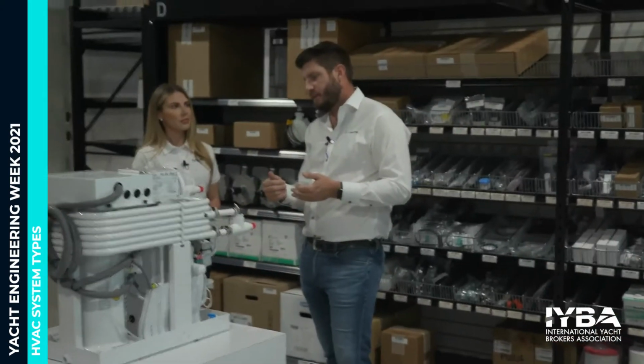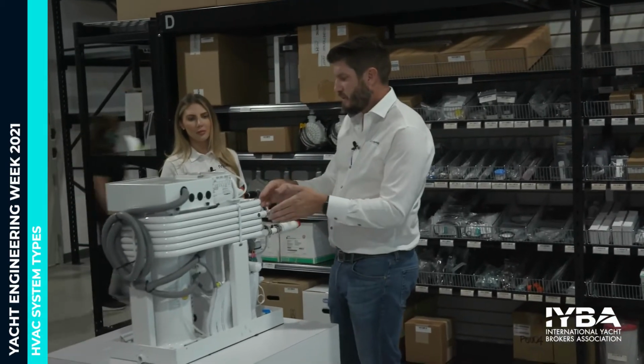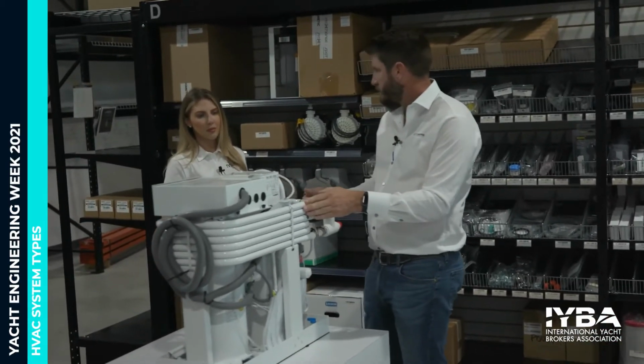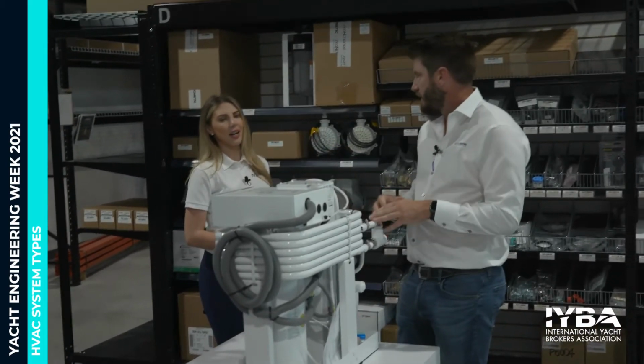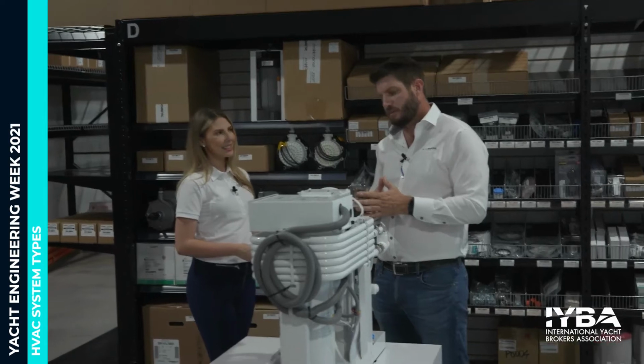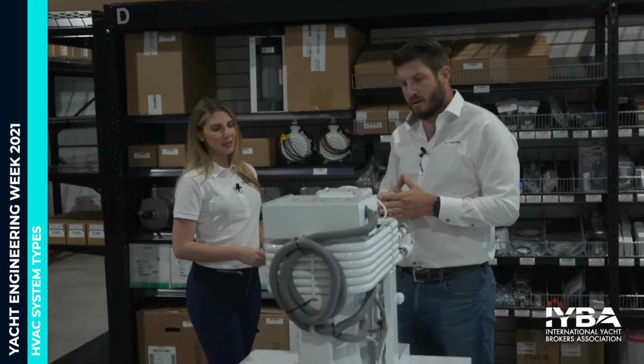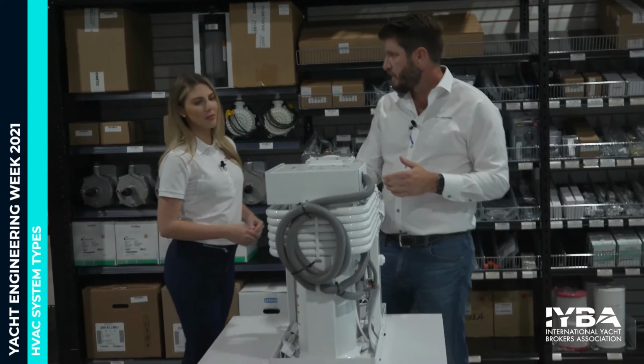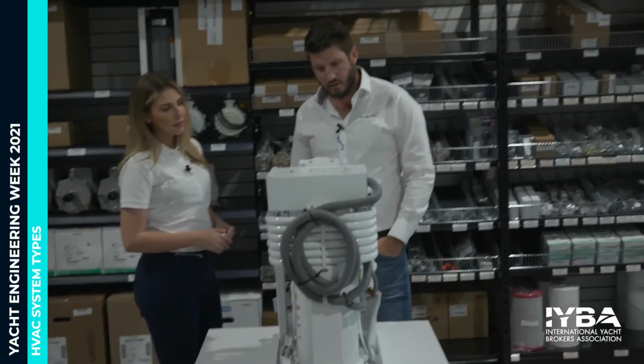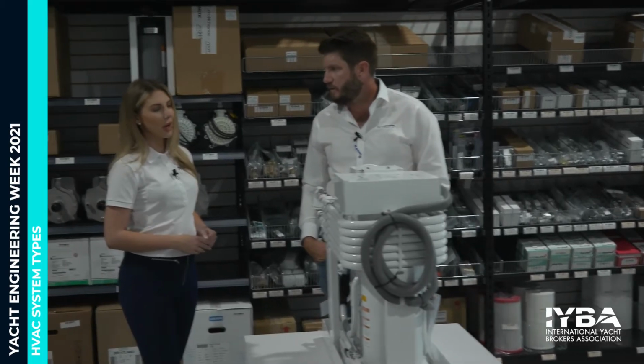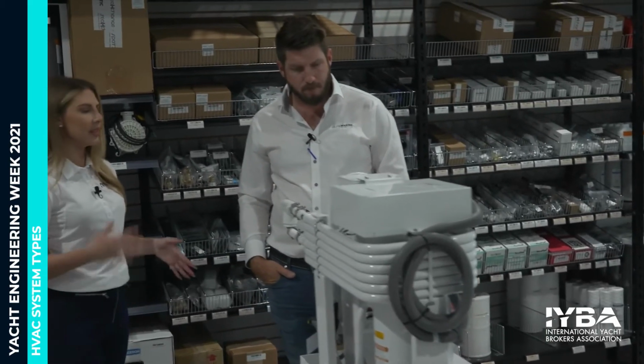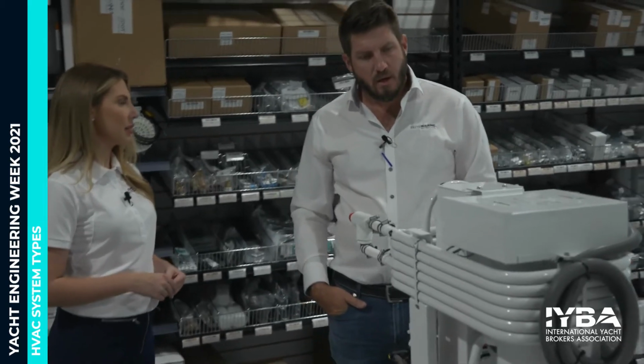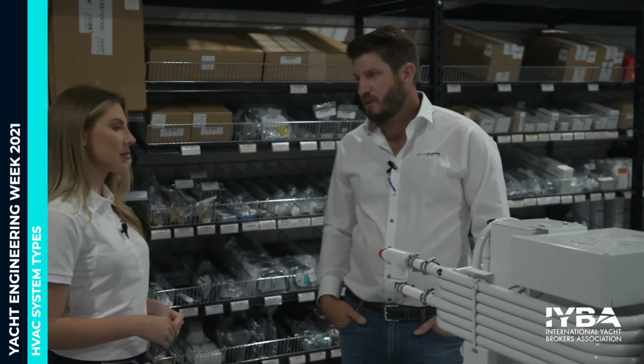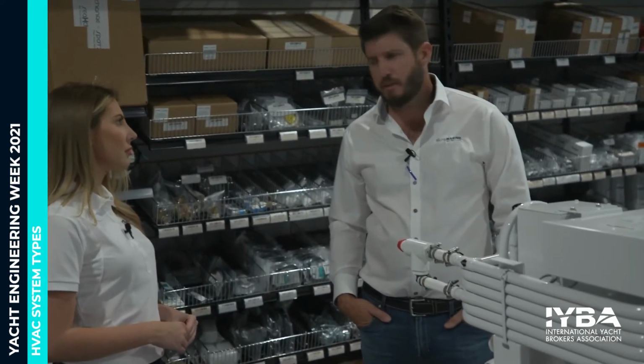So when the copper nickel fails, the refrigerant would leak out, and then seawater would get into the chiller, and the entire chiller would be trashed. So it was a big expense, big inconvenience. And so now a lot of the manufacturers are using titanium condenser coils, and they're extremely resilient to seawater, as you can imagine. What would you say the average maintenance or lifeline of one of these systems would be like? I would say previously 5 to 10 years with copper nickel. Titanium has been out about 3 or 4 years now. So we're probably going to see some chillers lasting 15, 20 years. Oh, wow. That's great.